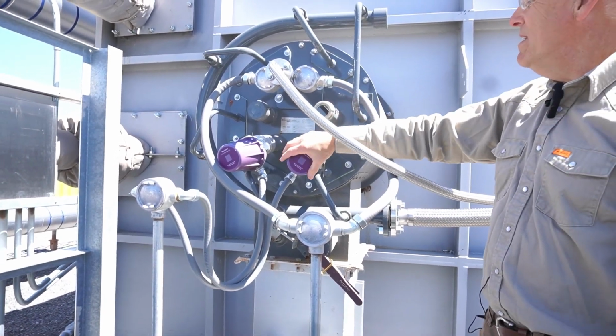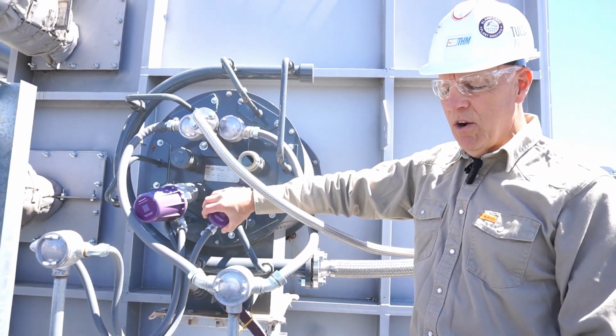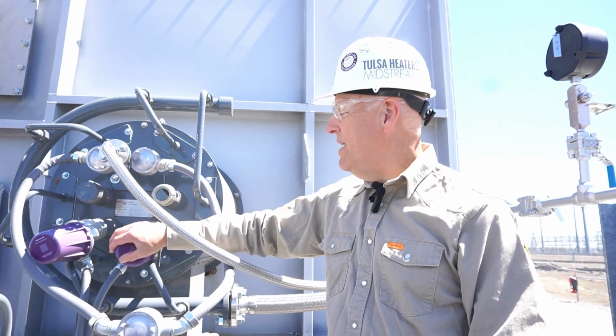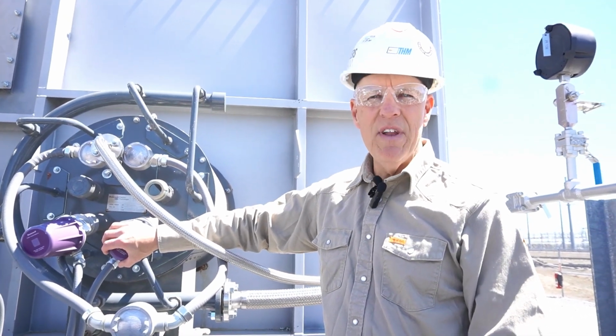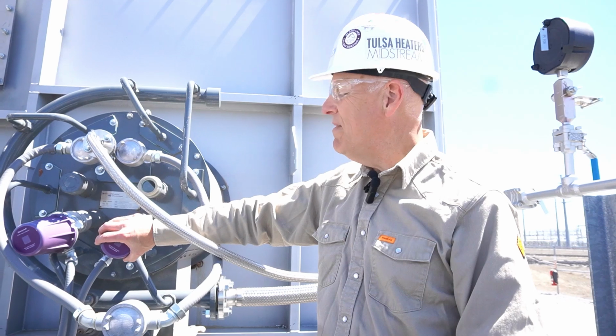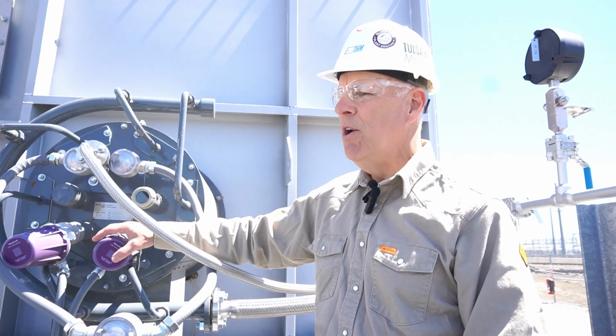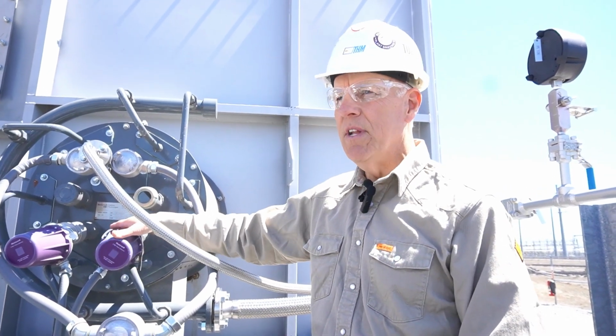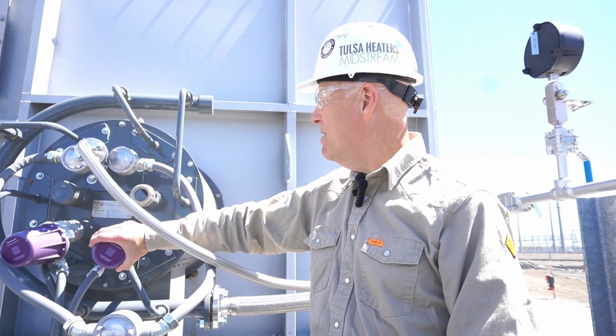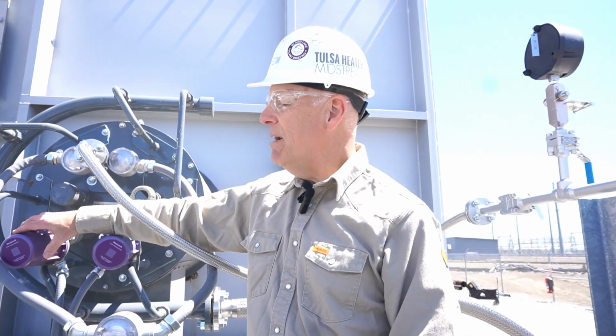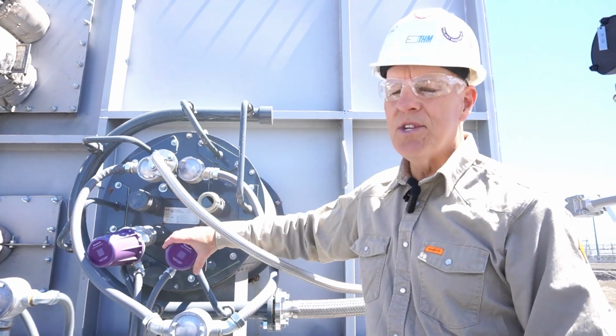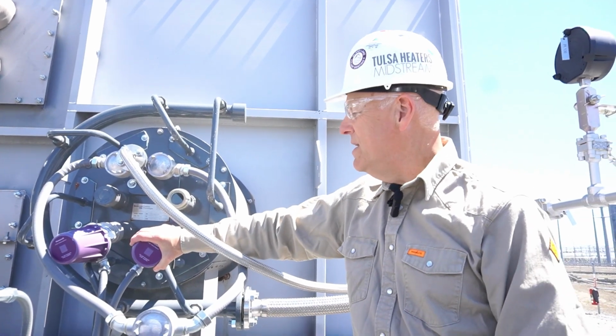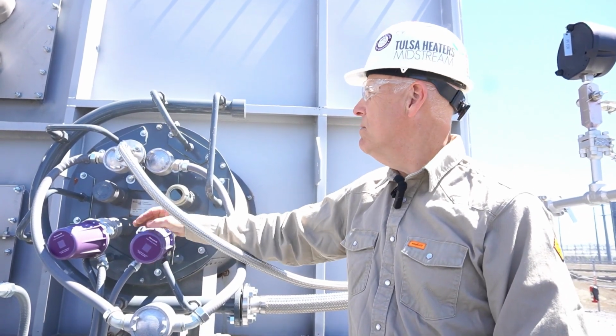One other comment, if something could go wrong, it's usually the scanner. Usually there's a problem sighting the flame. If there's a mechanical problem, if this thing vibrates and gets out of alignment, or if any kind of debris gets over the lens of the flame scanner, that can be a little bit of a pain. So if you got maintenance, it's usually the scanner needs to be adjusted to get a good, strong flame signal.